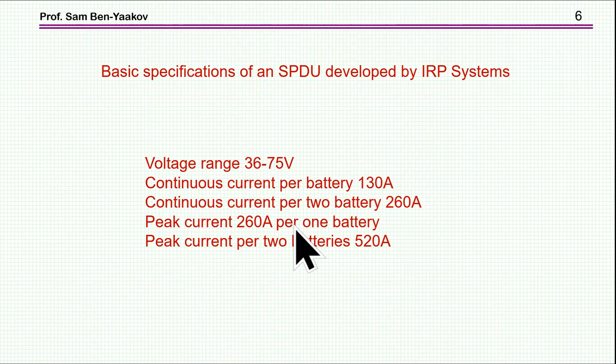So we have a number of types of battery that it can accommodate. We have a continuous current per battery of 130 amps continuous current, per two batteries double of that.